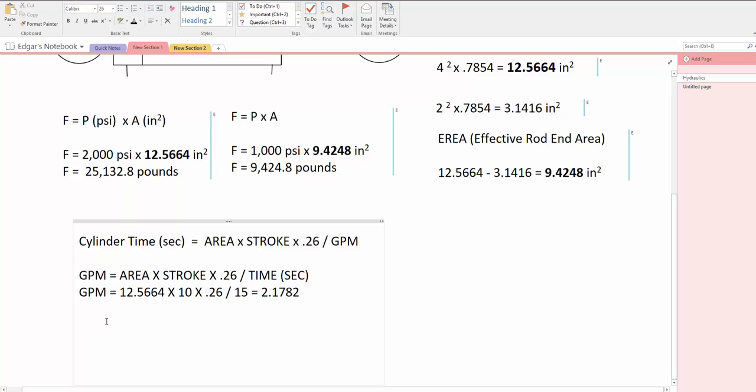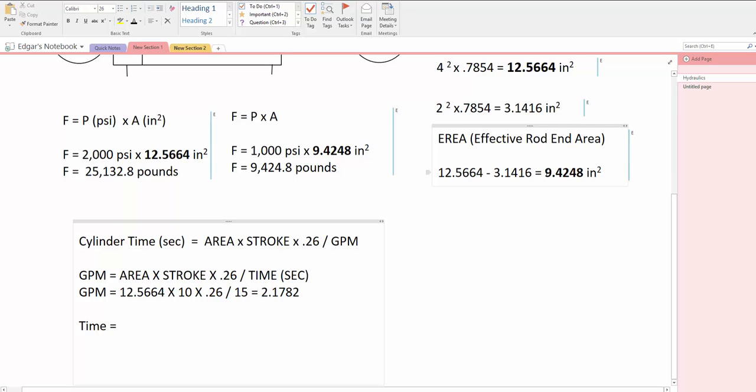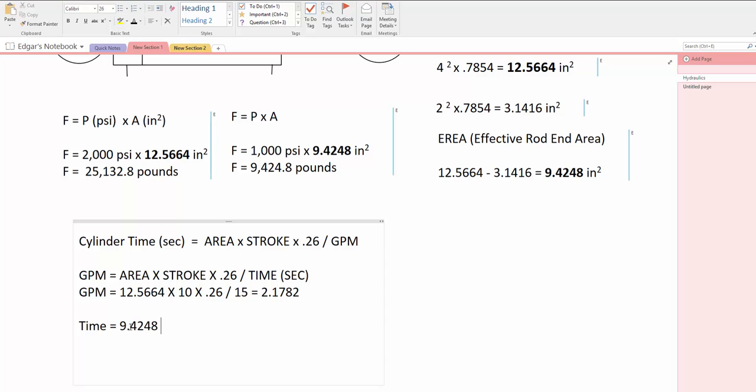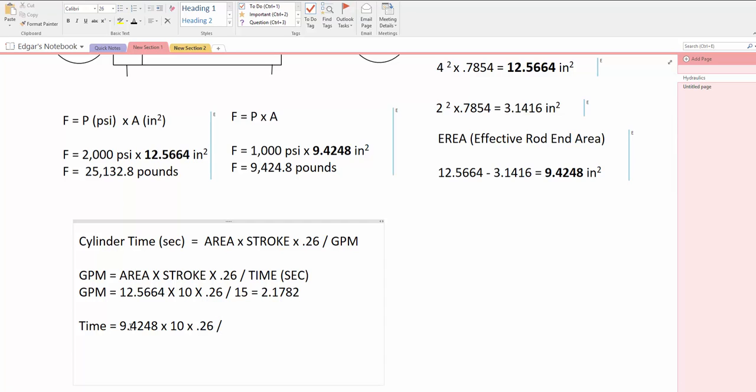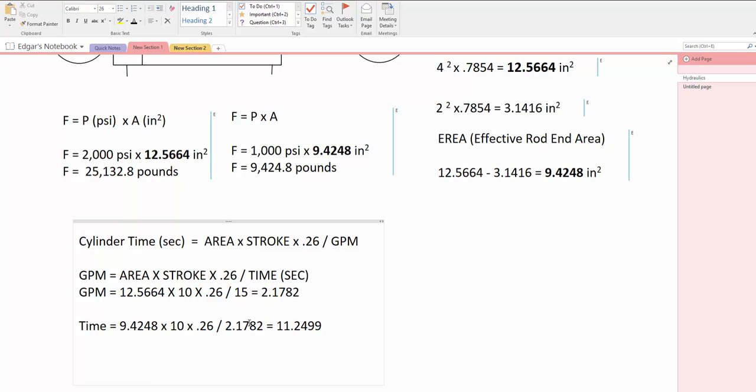time in seconds equals area. Now we take the retraction area and we say 9.4248 times 10 inches stroke times 0.26 divided by the GPM at this time, 2.1782. This equals 11.2499 seconds.